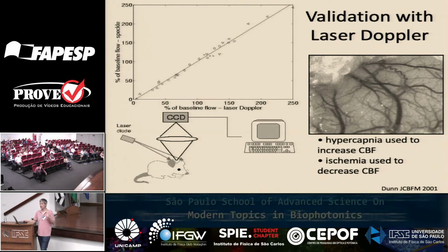For the diffuse correlation spectroscopy measurements, when we're making measurements through centimeters of tissue, we like to use lasers with coherence lengths of 1 meter or longer, just because the distribution of path lengths through the tissue can be tens of centimeters.